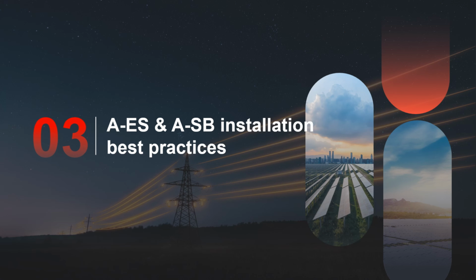Now, installation best practices for AES and ASB. The differences between these two inverters are mostly in the system architecture, with AES being DC coupled and ASB AC coupled. So beyond this point, I will speak in general terms that are applicable for both models. If there is a difference, I will highlight it. Also, a reminder that this training assumes that you are a licensed solar installer. I will only cover specifics to the GoodWe inverter. You will need to follow all of your local and electrical code as applicable.